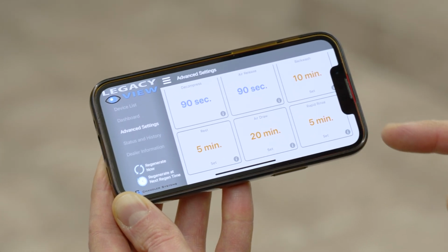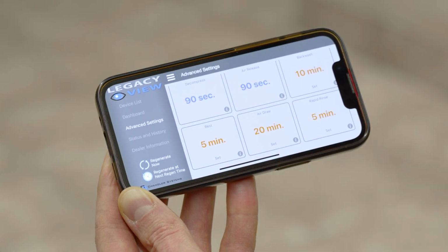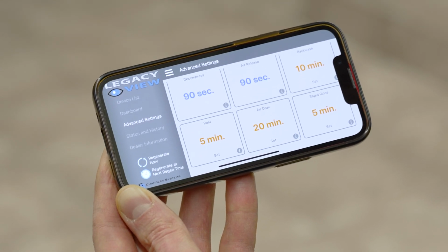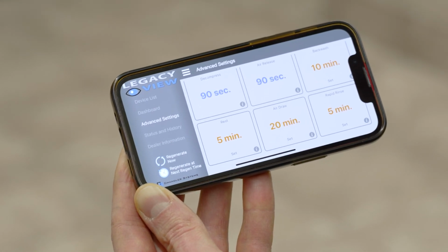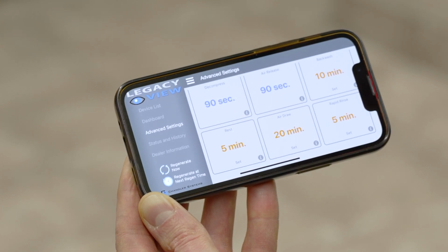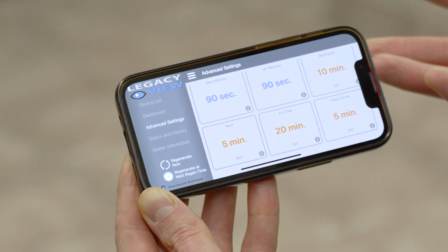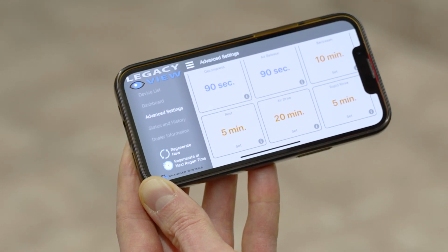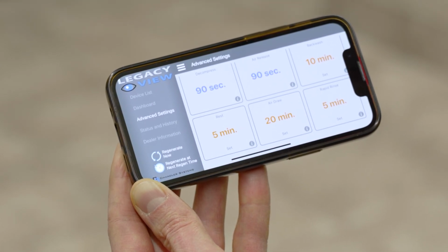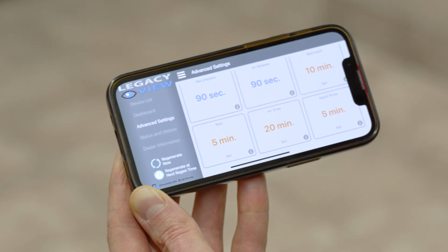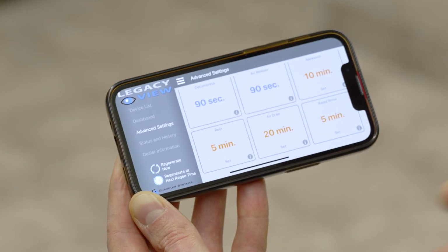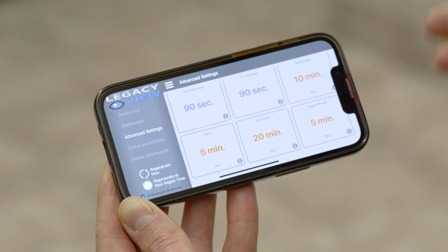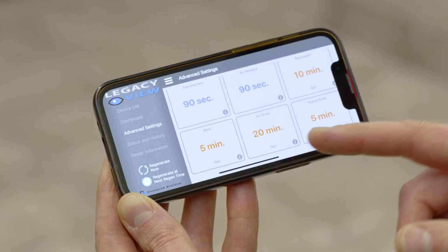The only ones you might want to change are the rest, which can be set to 0 if you don't have a low producing well. If you do have a low producing well, meaning a well that needs some time to catch up after running all that water to drain and backwash before it goes into the air draw and the rapid rinse, you could set that to a much longer time to give your well time to replenish. But if your well's got plenty of water, you can leave that at 5 minutes or zero it out. You really don't need to rest between these cycles if your well's got plenty of water available.